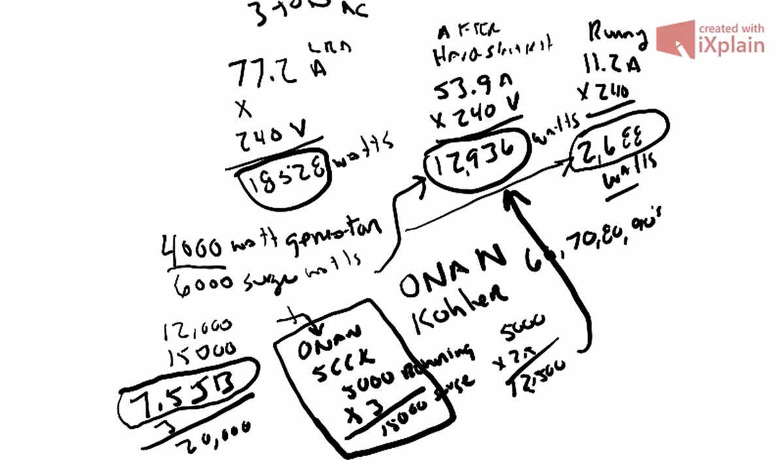You could also utilize load management and only start one thing at a time. And remember, once it's running, the wattage is a lot less. So if you look, I only need 2688 watts once that thing started and running. So if you had a 5000 watt generator, you would technically have some headroom. But the big issue is when these loads that require that have a motor that require a large amount of starting amperage, you want to have yourself some overhead.